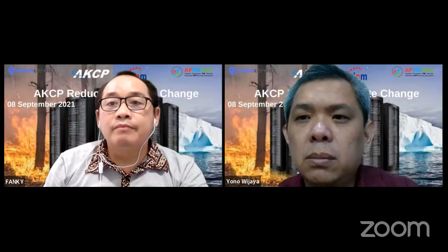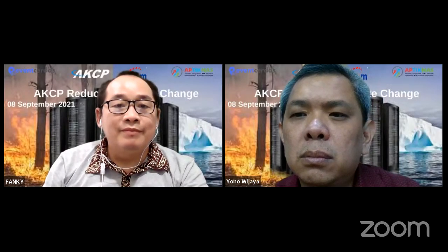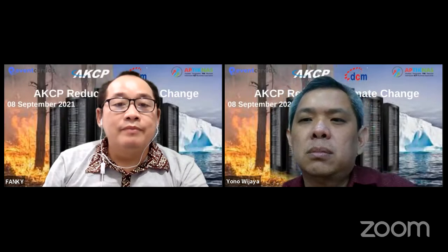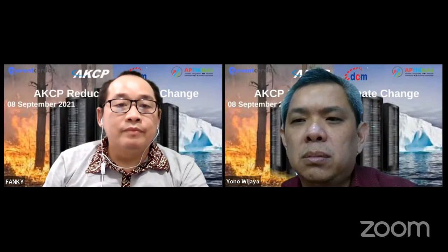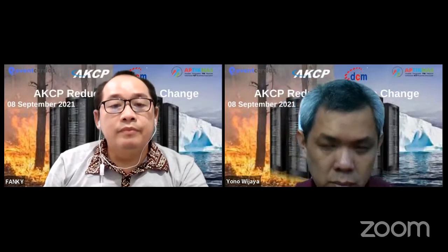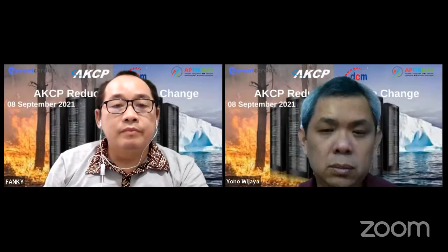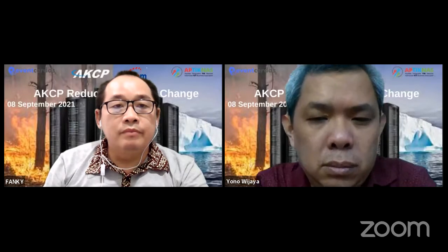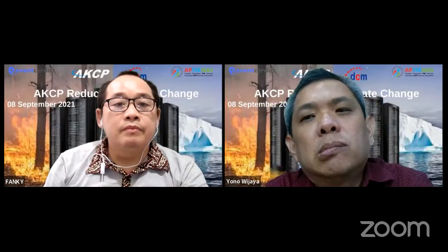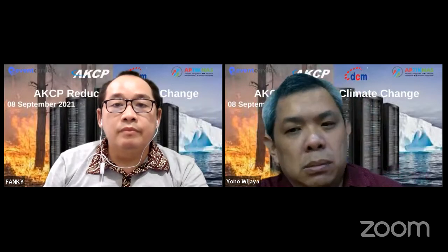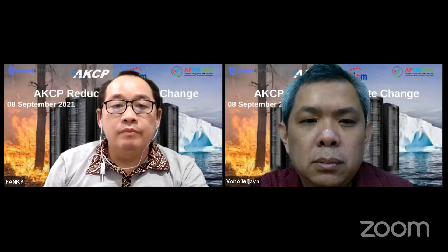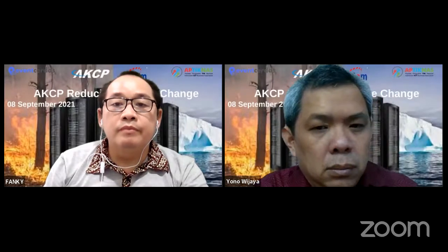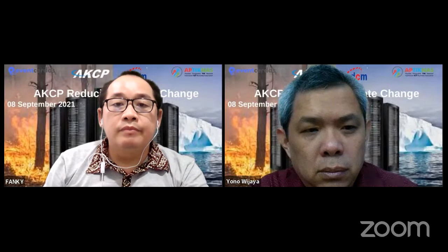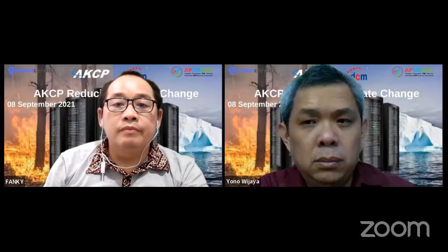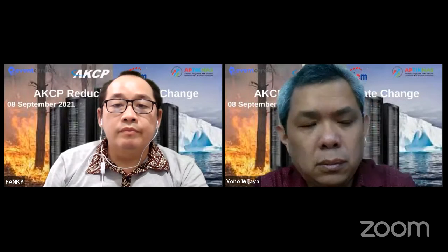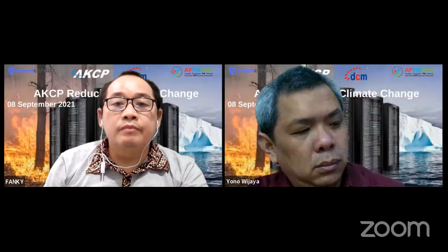Well, in Indonesia anyway, you're never going to get 100% free cooling with outside air. In fact, your outside air is going to be higher in temperature than just recirculating the air inside. I did mention that a PUE of 1.0 is really not achievable, even in a cold country, if you're doing it in Alaska, Norway, etc. Because you're right, you have to bring that air in with fans. You've got to suck that air in somehow, which is going to consume energy. And it has to go through filters. And you have to humidify the air. So a PUE of 1.0, 100% free cooling, is never going to be achievable.